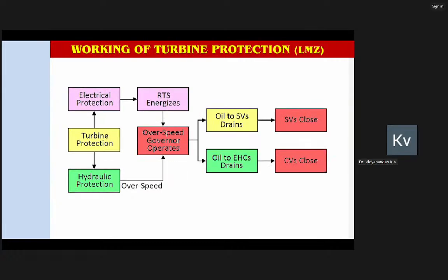Whereas in case of the 660 megawatt Russian turbine, it is almost identical. They don't call it trip oil. They don't call it auxiliary trip oil. They simply call it power oil. But for convenience, it is the same thing. Power oil means basically the oil which is going for the stop and control valve operation. That is the trip oil. And here there is one more aspect. In case of a Siemens machine, the same trip oil is routed to stop and control valves and NRVs. Whereas in a Russian turbine, they have a dedicated line for stop valve operation, another dedicated line for control valve operation. The feature is the same, only they have bifurcated the line, maybe for convenience.